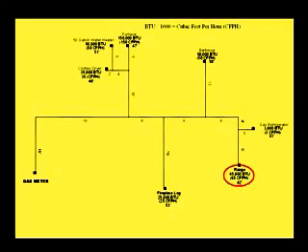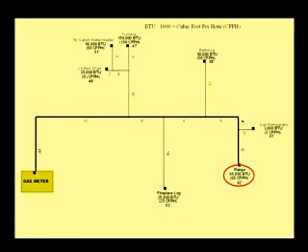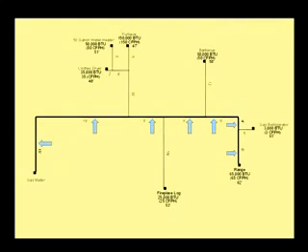The first step is to locate the most remote appliance from the meter. Based on adding up the lengths of pipe from the meter to each appliance, the range is the most remote. This will become the main supply line. We will now size the entire main supply line starting with the most remote section and working back to the meter.